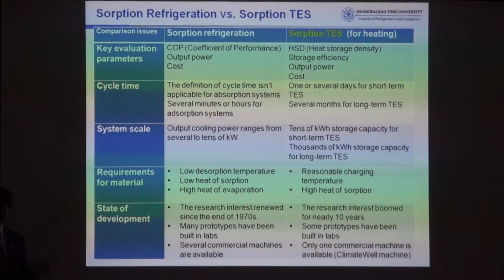So there are 2 examples. We show short-term thermal energy storage, for example, 10 hours or so. For example, this shows charging at night in the winter time. We use the heat from the network to generate zeolite water and to make the zeolite dry during the night. It is used for the office building, for example. During the day, we could use the absorption heat, and this heat could be output to the building for heating. So this is actually one scenario: thermal energy storage used only for several hours in 1 day, or just half a day, for example.